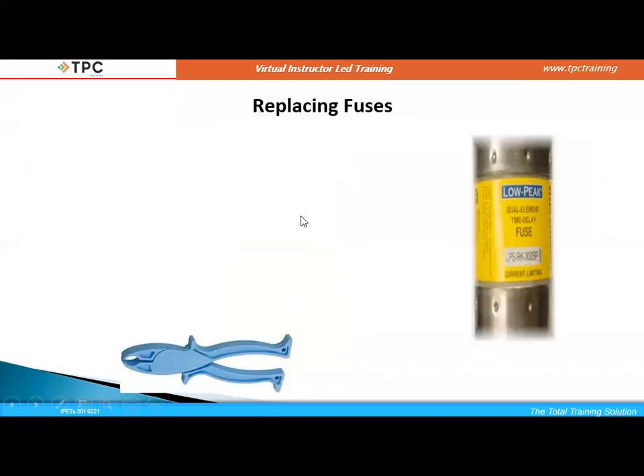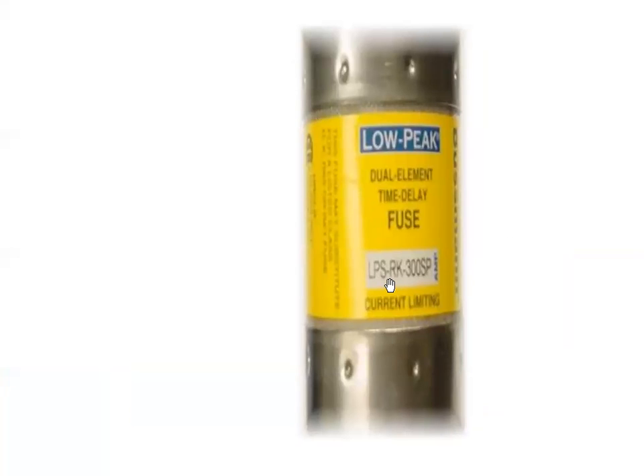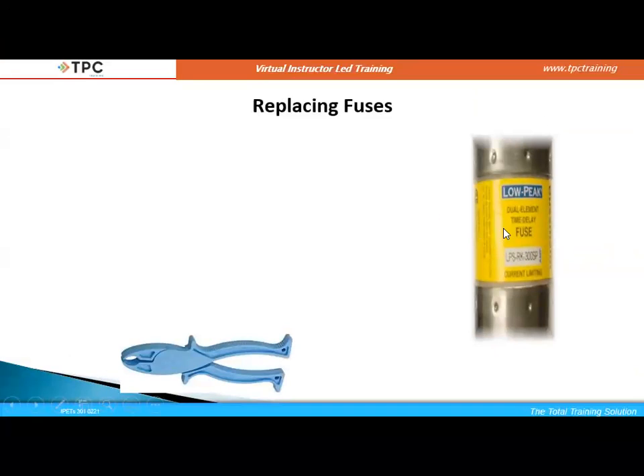If I am going to replace those fuses, here is a picture of the insulated fuse puller. They also make a yellow one. But let's take a look at this fuse over here just for a second, and I'll zoom in on it. LPS, RK, 300 SP, current limiting, dual element, time delay fuse, low peak. Low peak sensing right off the bat. What does that mean? That means that our sine wave will not even get a chance to get to the peak before this fuse is going to open up and protect that circuit. That happens extremely fast, in even a half a cycle. So if we replace this fuse, we're going to lose all those characteristics of that fuse, and we've got to replace it with the exact same type that is in there.